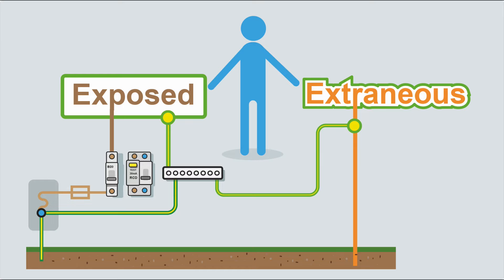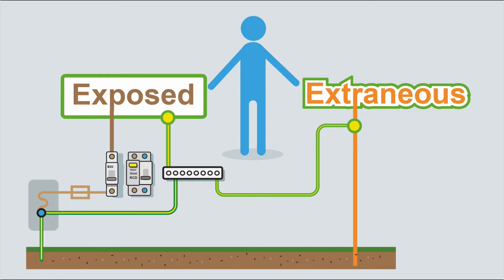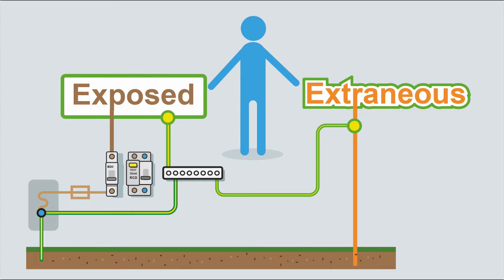I'll quickly go through extraneous and exposed conductive parts - I have got a video on this which I'll link to. An extraneous conductive part is a conductive part liable to introduce a potential, generally earth potential, and it doesn't form part of the electrical installation - that's your gas pipes, water pipes, steelwork and such. An exposed conductive part is a conductive piece of equipment which can be touched and which is not normally live but can become live under fault conditions - that's your electrical things: light switches, boilers, immersion heater, anything connected to the supply.